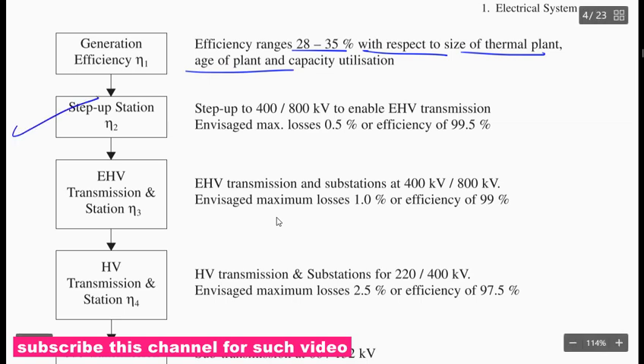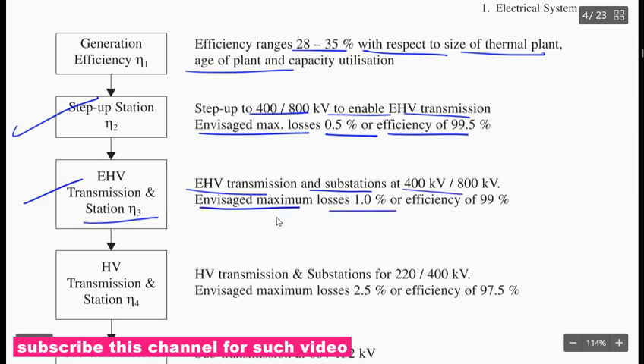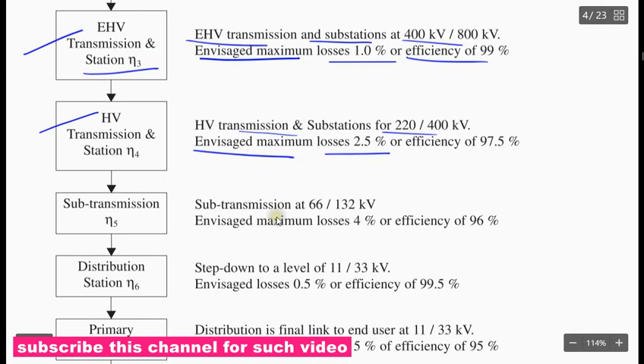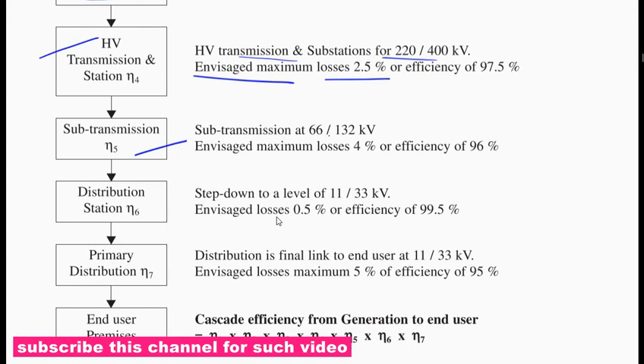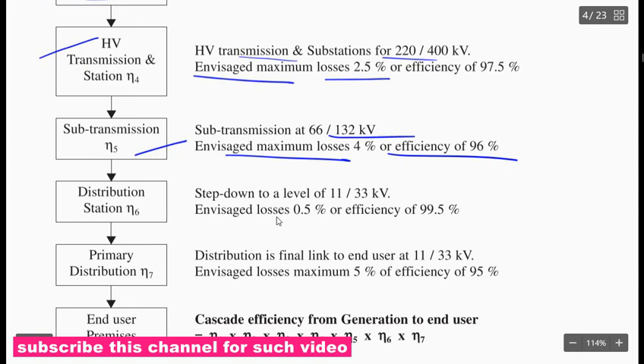Then step up, 400 to 800 kV, to enable the extra high voltage transmission line. Maximum losses 0.5% and efficiency 99.5%. Extra high voltage transmission and substation, 400 kV to 800 kV, envisaged maximum losses of 1% and efficiency of 99%. High voltage transmission and substation, 220 and 400 kV, maximum loss is 2.5% and efficiency 97.5%. Substation next, 66 and 132 kV. Maximum loss is 4%, efficiency is 96%.